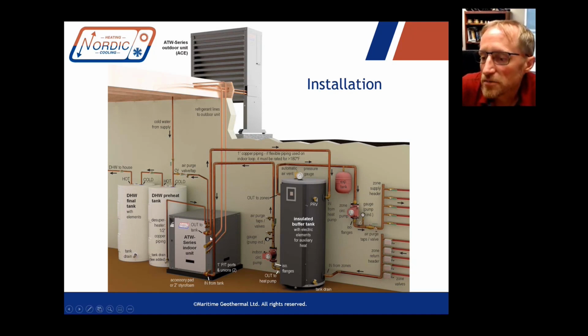Of course, the main job of the heat pump is going to be to heat or chill a buffer tank. There can be 2 buffer tanks, as I mentioned, and it can automatically switch back and forth to heat a hot tank and chill a chilled tank. Most people just have 1 buffer tank and do a seasonal switchover. So these are the main outputs. The water lines from the heat pump are these 1-inch lines here, connected to the buffer tank.